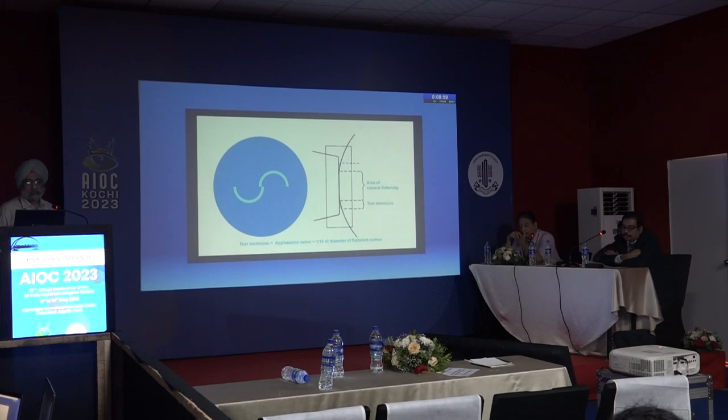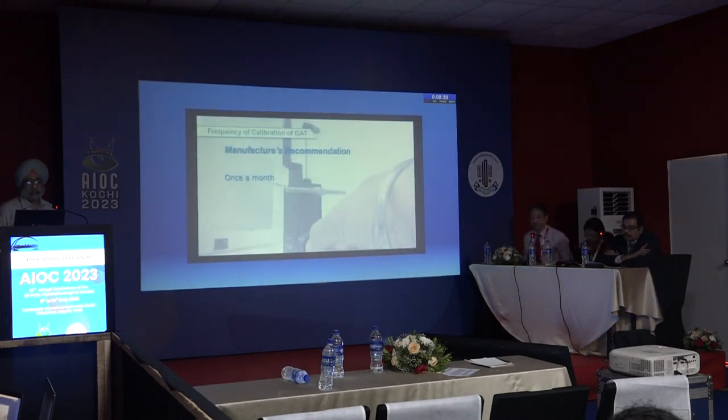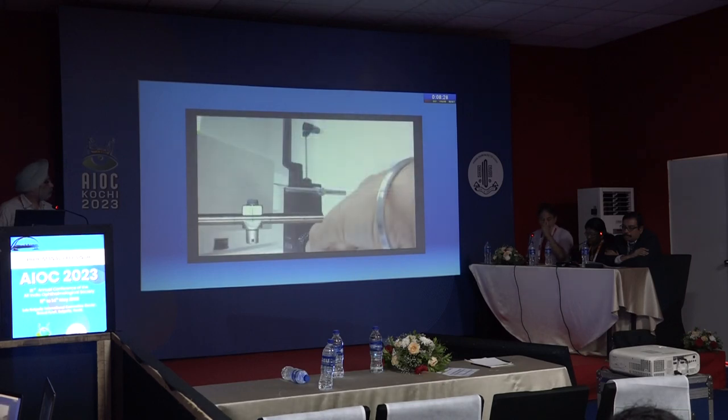It is essential that the thickness of the wires should be around one tenth of the total diameter of the flattened area. Prolonged contact of the prism with the cornea can lead to corneal injury and reduction of IOP, and should be avoided. For calibration, although manufacturers recommend a once-a-month check, the general consensus is that three to six monthly checks depending on the instrument's age is sufficient. Calibration is performed at scale readings of zero, two, and six.